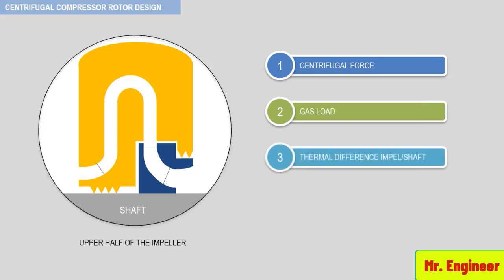Thermal difference between impeller and shaft, and thrust force. The impeller must be designed such that the shrink fit, so the shaft diameter minus the impeller bore diameter, is sufficient enough to maintain impeller shaft contact at maximum conditions. So the amount of shrink fit required for impellers can become large.